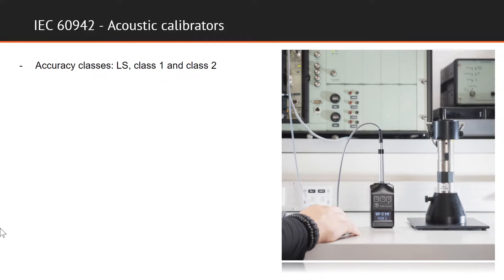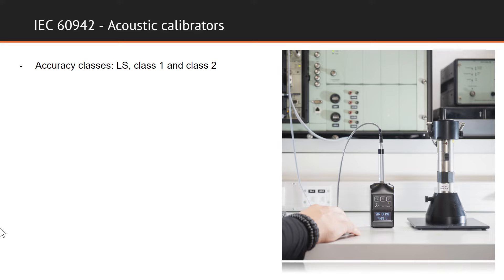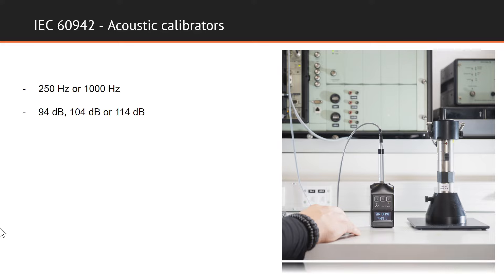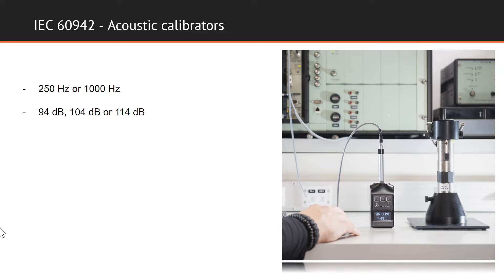This standard defines three classes of accuracy: LS, 1, and 2. Class LS is intended for laboratory use, while class 1 and 2 are intended for field use. Calibration is performed at a single frequency, either at 250 or 1000 Hz, and at supported acoustic pressure levels, which are usually either 94, 104, or 114 dB.